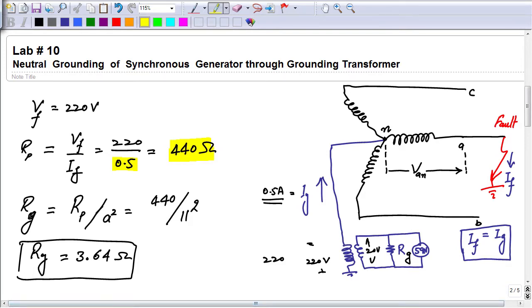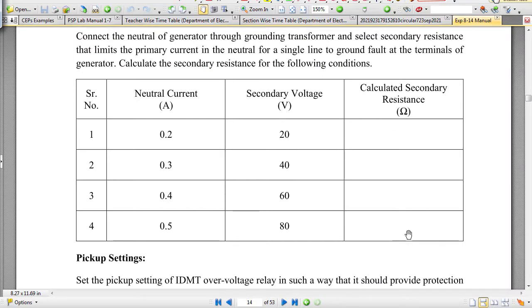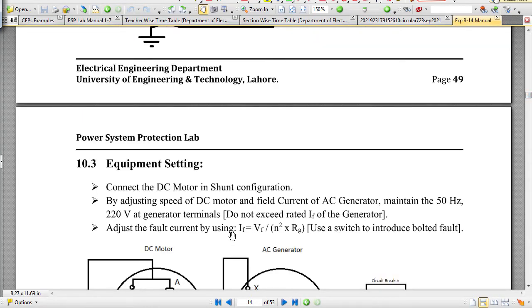So this is how the first step will be done by the student to fill out this table. For different values of the secondary voltage and the fault current, they will calculate the resistance value. The generic formula has also been given over here. This is the formula to calculate the value of Rg. IF is known to us, VF is known to us. We will calculate the turn ratio squared, that is N squared, the transformer ratio squared, multiplied by Rg. So we can solve this equation for the unknown value of Rg if IF and VF are given to us. Here VF is taken as the primary voltage.